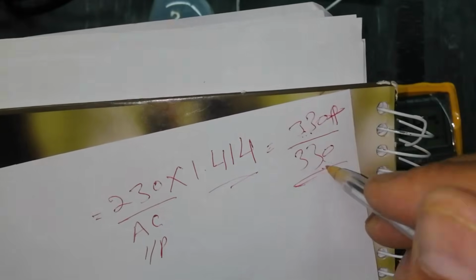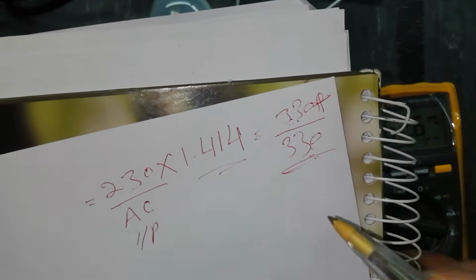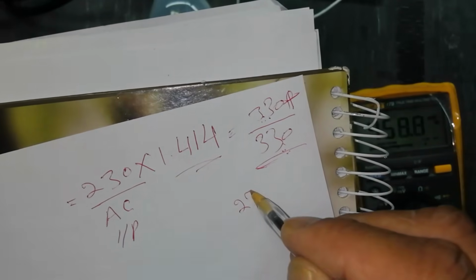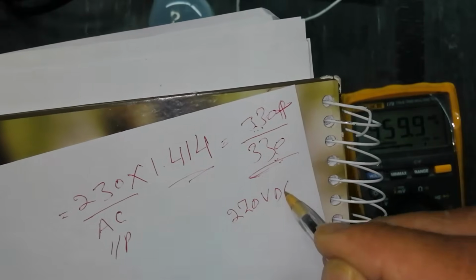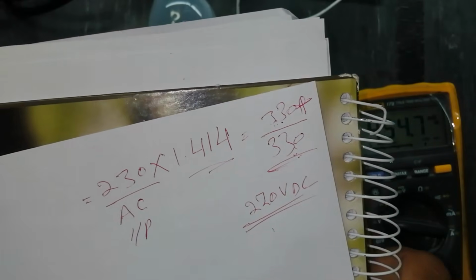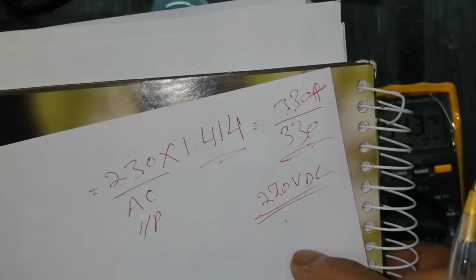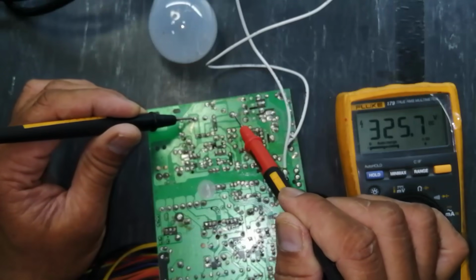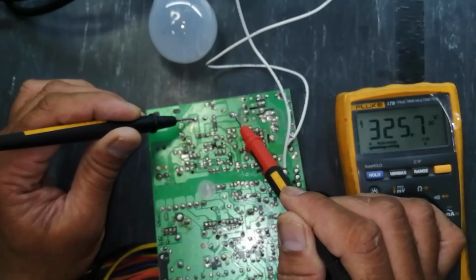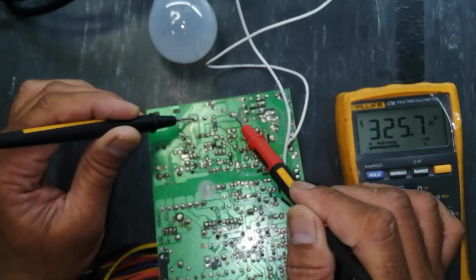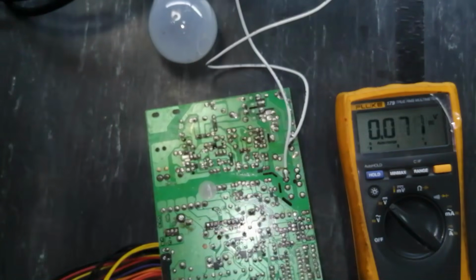If you don't find that voltage - for example if you find 220 volts DC, that means we have a problem. 270 volts DC means one capacitor is bad. Here I have 325 volts - that's good, that means our circuit is working.